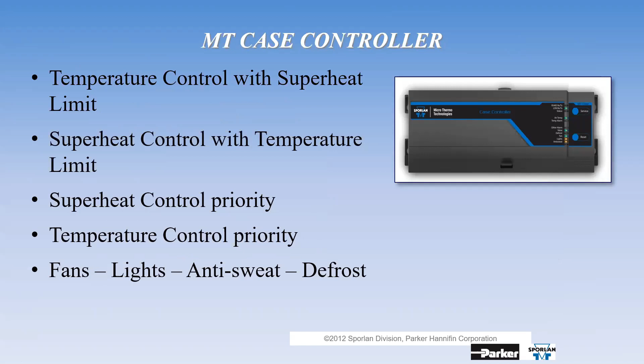I've already got ahead of myself. These are the ways that we control the case controller. And trend graph is in there. We optimize it by fixture. We optimize it by valve type, base value correction, maximum percentage open. What do I mean by that? After I start a store up, Nate, if I go into a case and I see that valve never, ever, ever goes past 38%, ever.